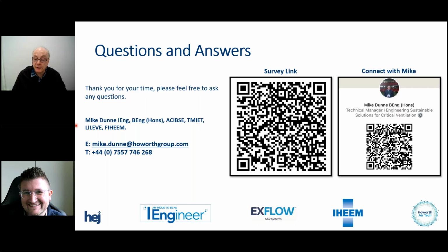Somebody's asked, HTM guidance suggests that ventilation in theatres continues to run in the event of fire condition. It says duct smoke sensor shuts off if required. And then has asked, how do you anticipate the fire damper in the slab will be operated to ensure triggering by fire alarms does not disrupt the desired continued airflow?